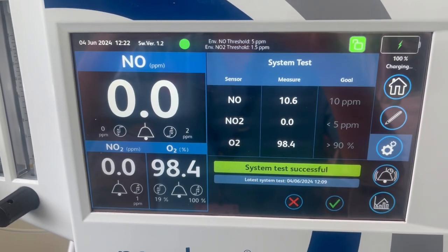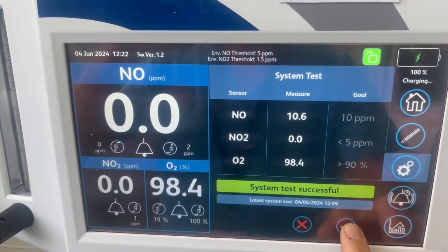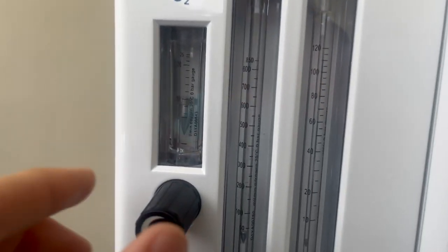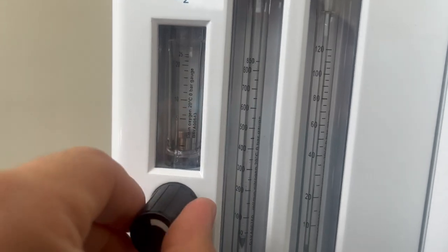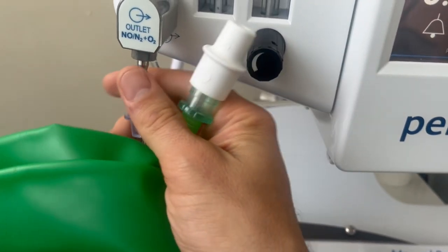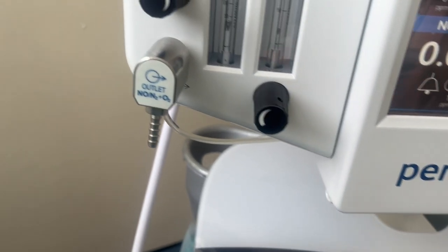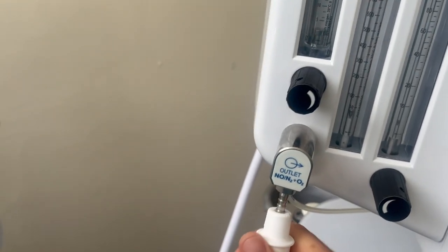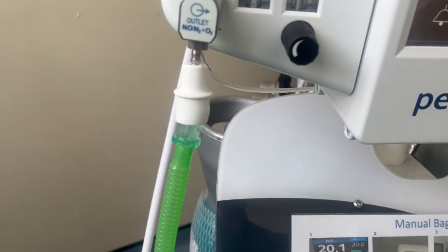When the system delivery test is successful, press confirm and turn off the O2 flow meter. You can now remove the test circuit connection and connect your means of bagging the patient, your water circuit or Mapleson C circuit.